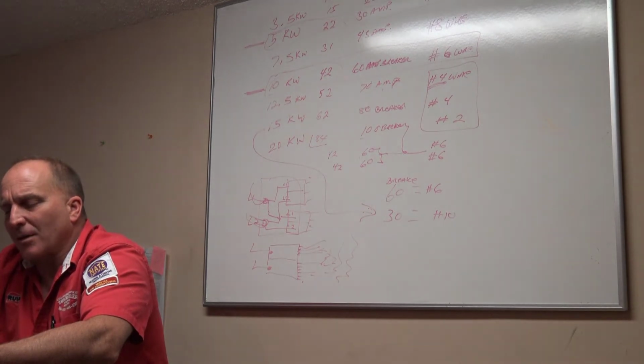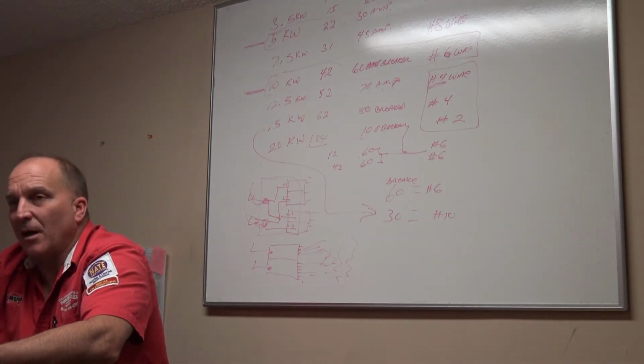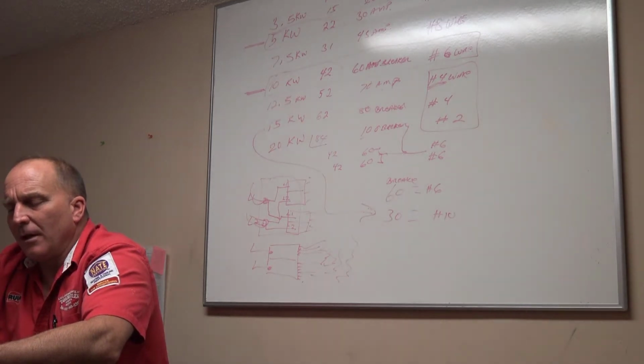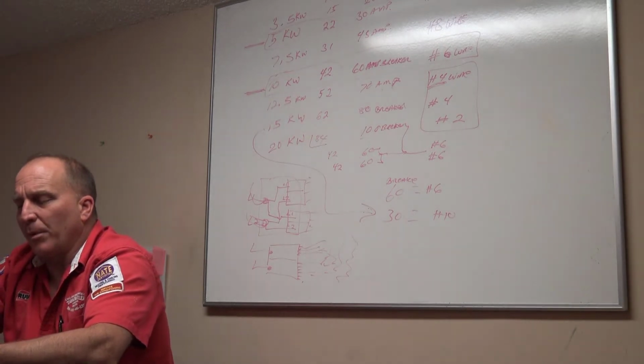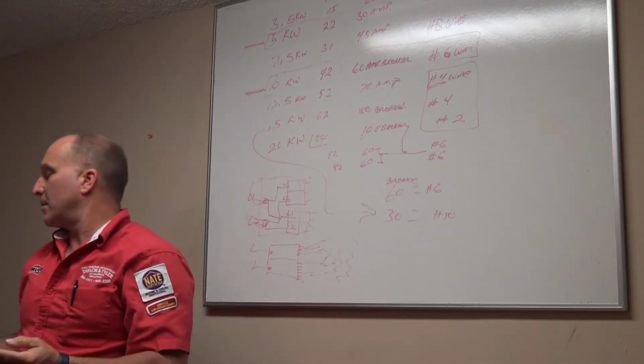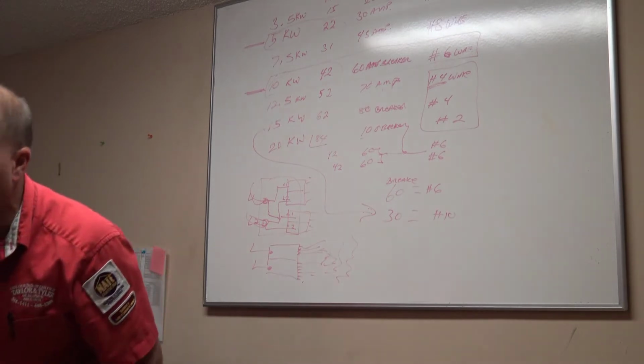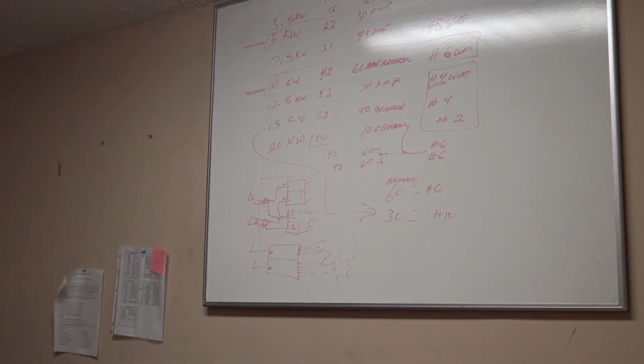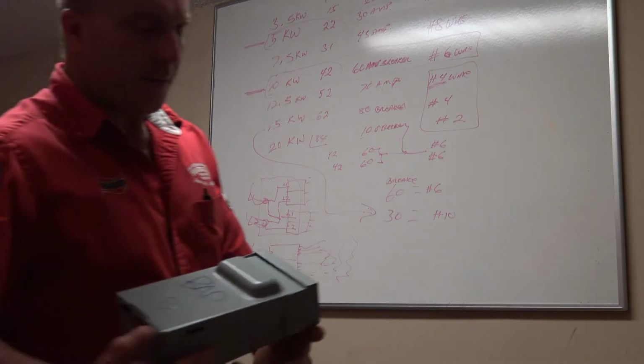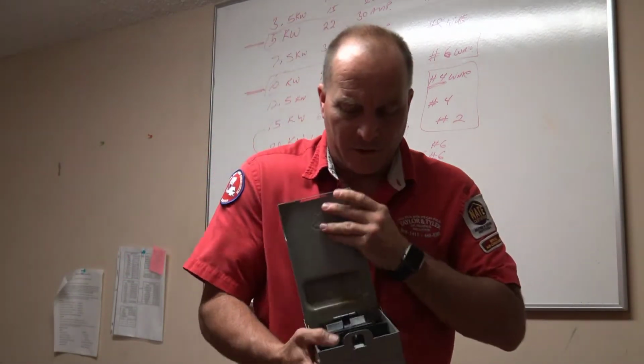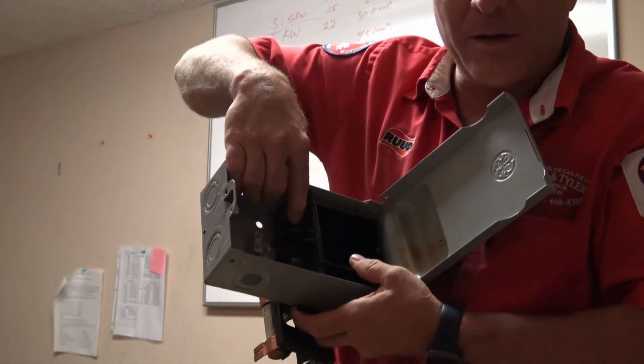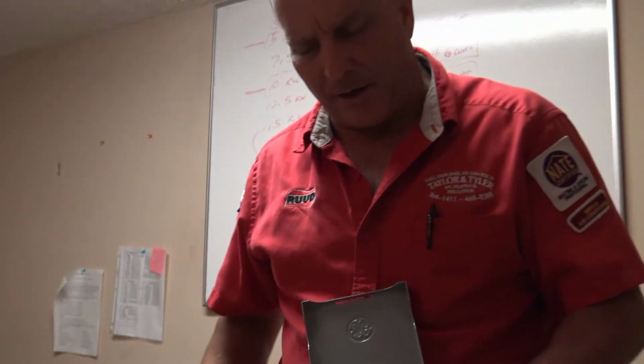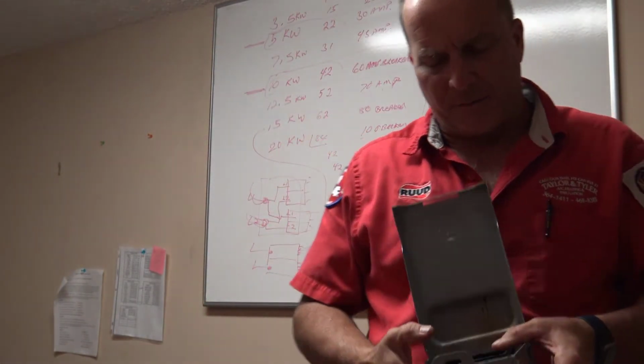Replace the disconnect box with a breaker box and obviously cut back the wires. If the fuse block is broken, like in 2 pieces, then replace that fuse box with a disconnect box with a breaker. So this is an example of a bad breaker box, okay? In this box here, you have a pullout. I know you probably can't see it in there, but this particular one is discolored up inside of here. When I look at it, I can see it's rusted and discolored.